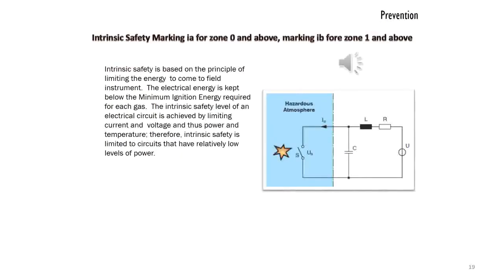Intrinsic safety marking IA for zone 0 and above, and marking IB for zone 1 and above. Intrinsic safety is based on the principle of limiting the energy to come to field instrument. The electrical energy is kept below the minimum ignition energy required for each gas. The intrinsic safety level of an electrical circuit is achieved by limiting current and voltage and thus power and temperature. Therefore, intrinsic safety is limited to circuits that have relatively low levels of power.